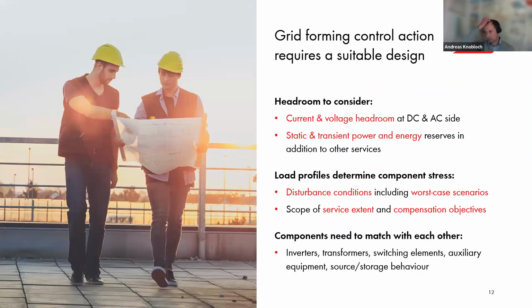An important aspect for grid forming system design is that the grid forming control action requires a suitable design. So inertia provision, synchronization provision typically has as a consequence a power exchange with the grid. And this power exchange requires some reserves for being provided. This might include static and transient power and energy reserves, in addition to other services that you would like to provide with your power plant. And it also requires some headroom to consider, current and voltage headroom, not only at the AC side, where you would like to provide your grid forming capability, but you need also to care about the DC side and the DC source, its behavior and the dynamics on it, for being able to perform grid forming control action.